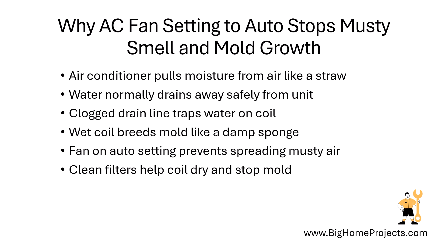A really common mistake is ignoring the smell because people assume it will just go away. But mold can actually grow quickly, so the fix is to schedule a professional cleaning before it spreads further into your ductwork. Another misconception is thinking a musty smell always means something is broken, when really it is often just a simple maintenance issue like a clogged drain line. So checking that drain line yourself or having a technician flush it can solve the problem fast.